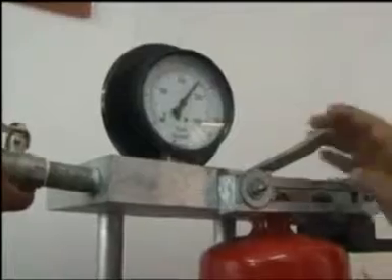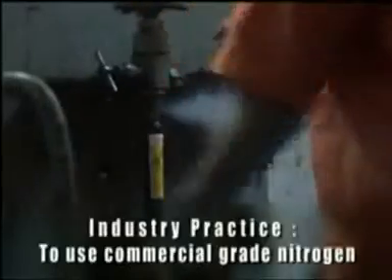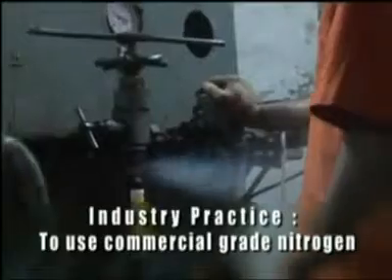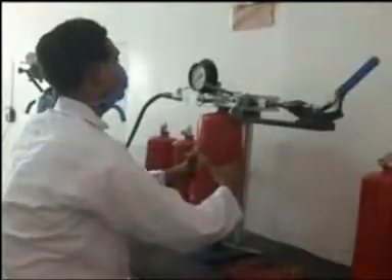Let's move on to the sourcing of the nitrogen propellant — the gas that drives the powder out with a certain force. The critical factor here is purity. Low-grade nitrogen could introduce moisture into the extinguisher powder, causing it to cake and clog. All Indian manufacturers use commercial grade nitrogen, whereas ceasefire uses high-grade nitrogen of a purity that prevents moisture from entering the extinguisher.